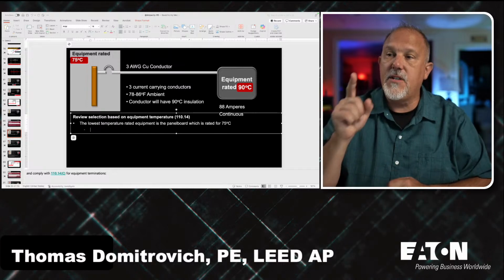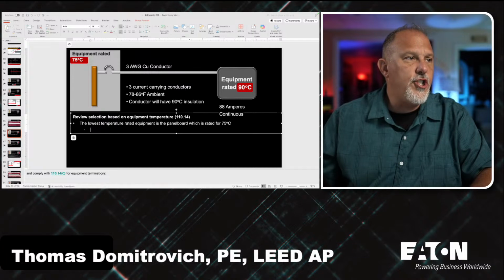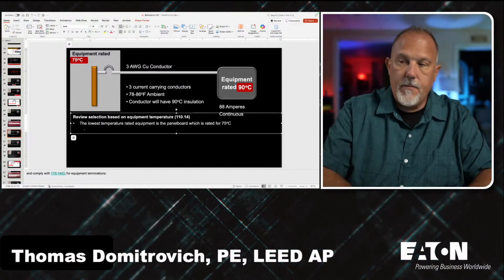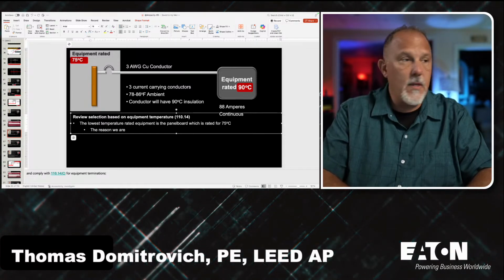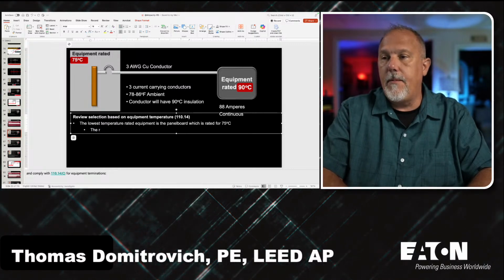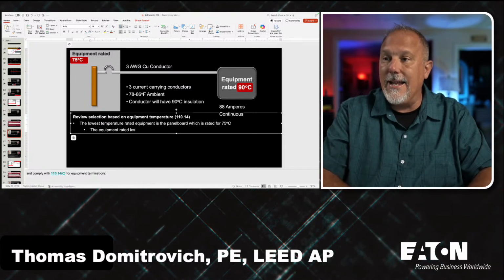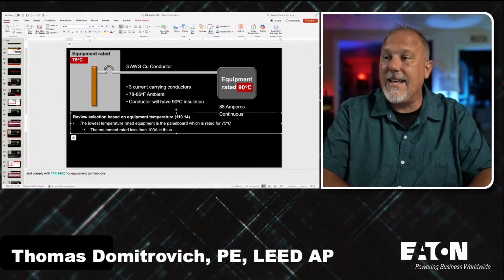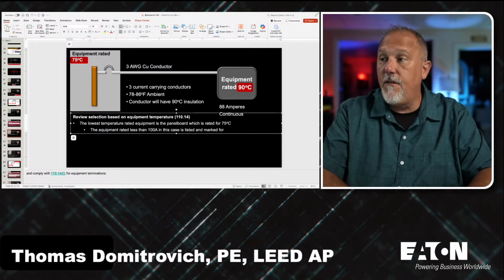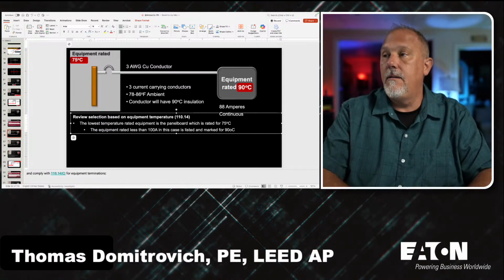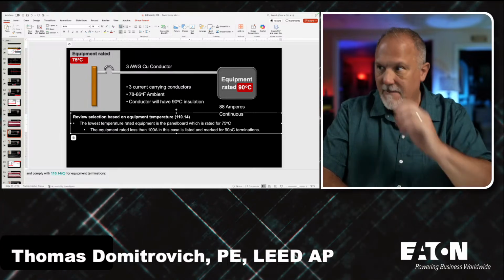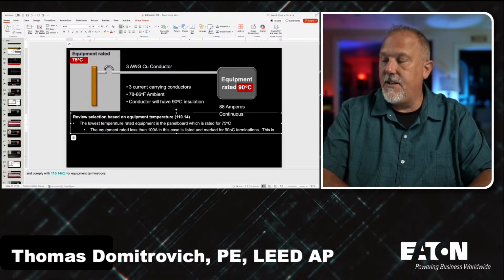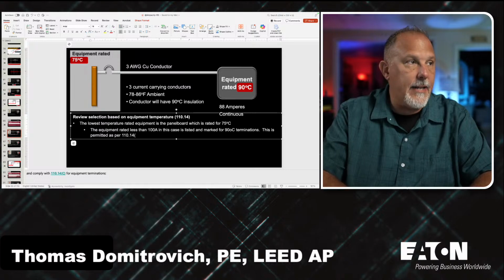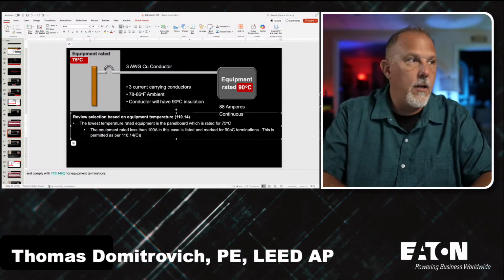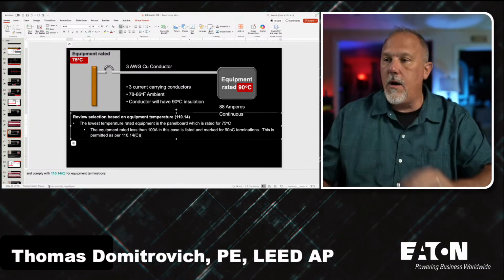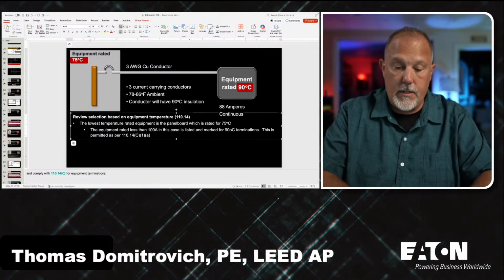The reason that I am saying that the equipment rated less than 100 amps, in this case, is listed and marked for 90 degrees C terminations. Okay? This is permitted as per 110.14, Charlie, I think it's C. Yep, C1, A, oh boy, 3.